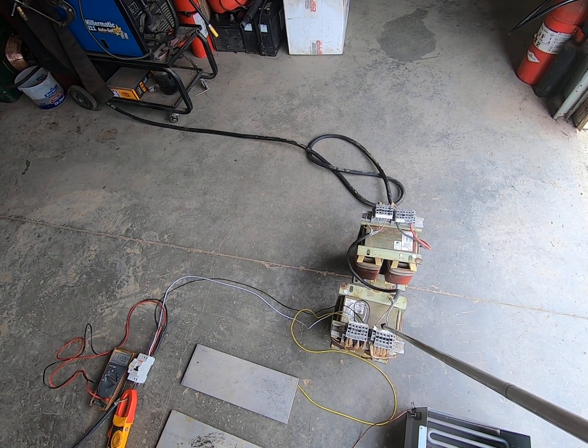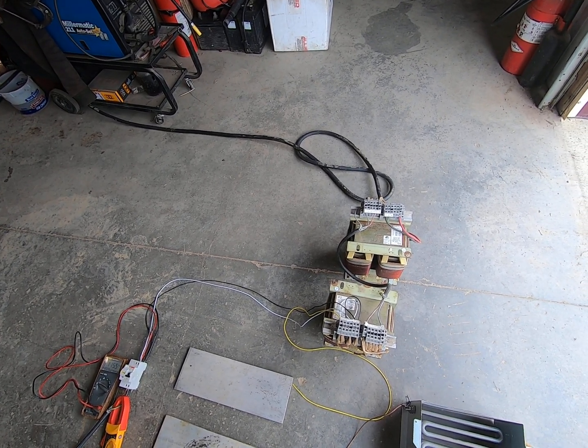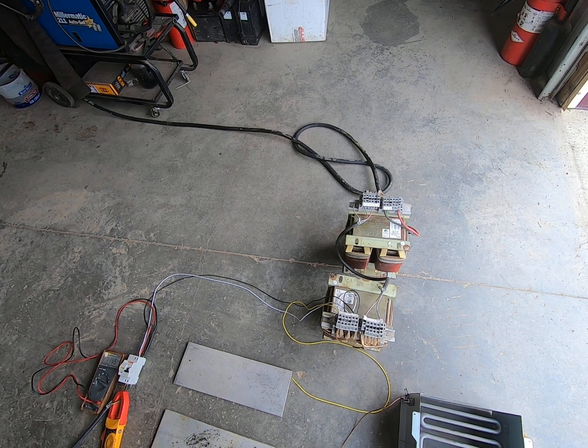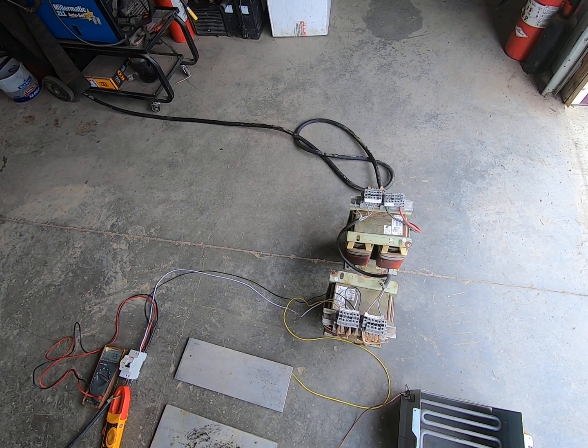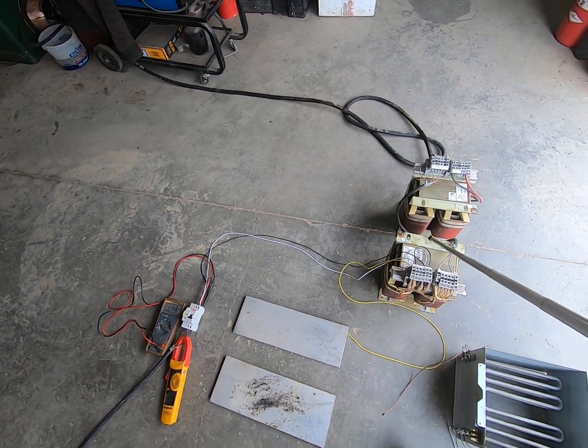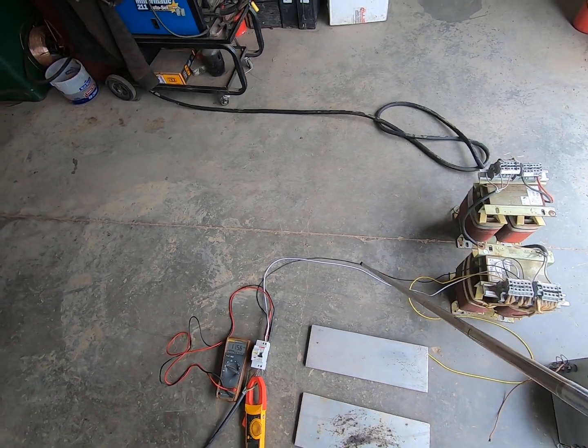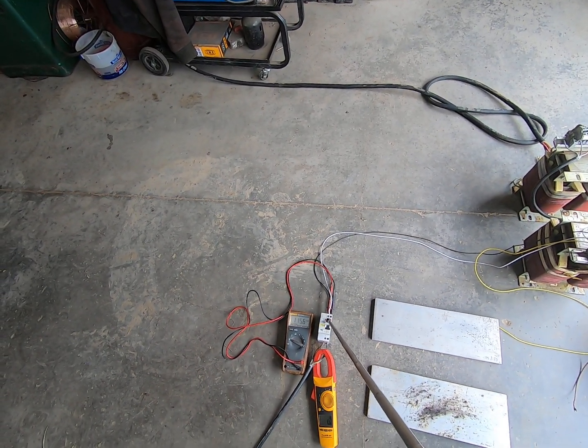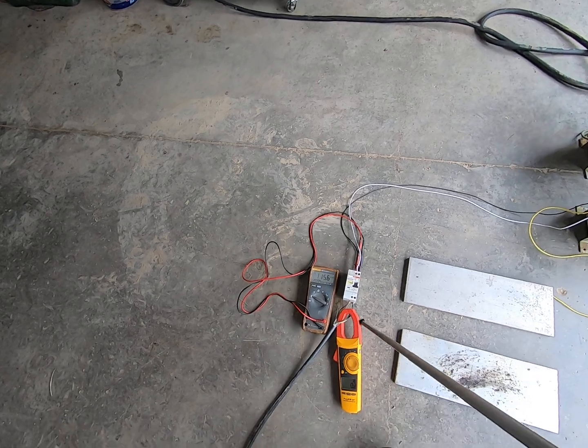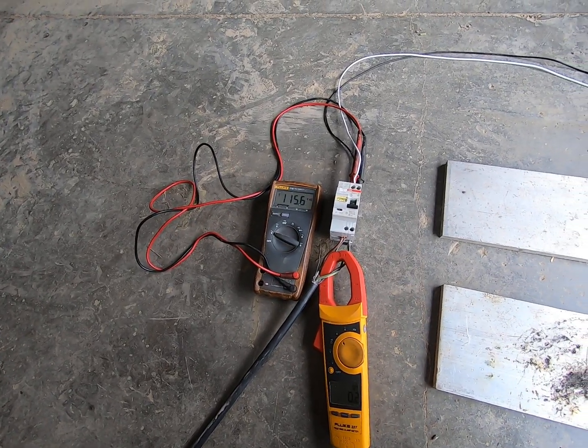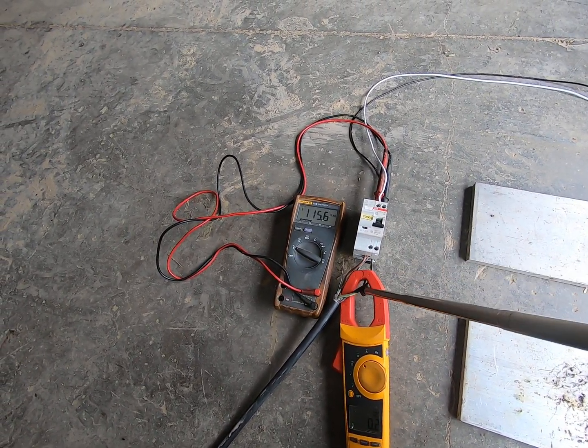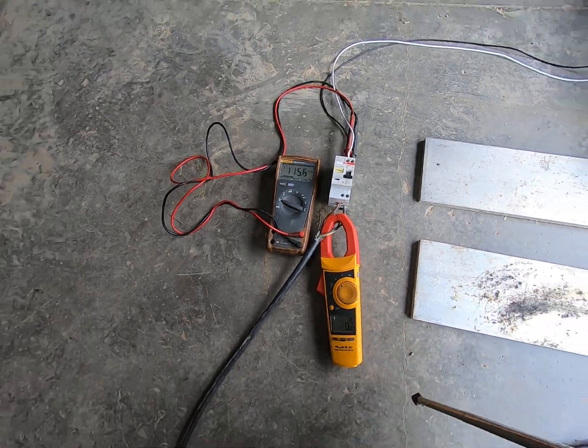690 is then feeding this other transformer, and I'm putting out 120 volts. The reason I did this is to create a separately derived system, which would be similar to what the turbine has. This transformer, the 120 volts, then feeds the breaker. We're actually at about 115 volts now. Breaker then feeds this cable. I've got an amp clamp on it.